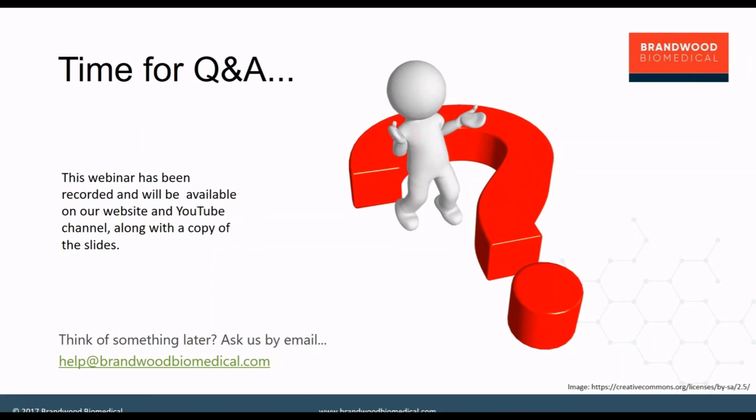Question from Zhang. Do you need to include all test reports in the technical file? You do not. Again, the primary purpose of the technical file is to demonstrate compliance with the essential principles. What that means is that most of the essential principles will relate to the final product, the top level product, so your system.